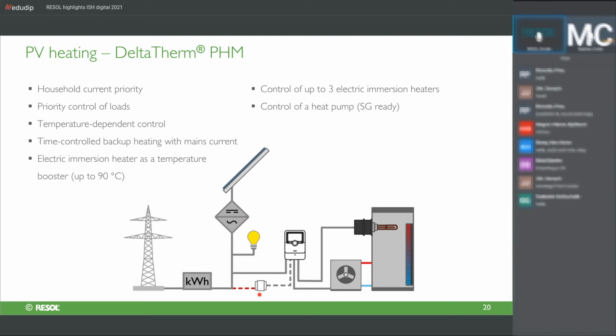In such an example with a heat pump and one or more electric heaters, a temperature-dependent control would be used. First, the heat pump would be activated and used for the lower temperature range. Only later, when we get into the warmer range where the COP of the heat pump gets worse, the heating element would be switched on and act as a kind of temperature booster.